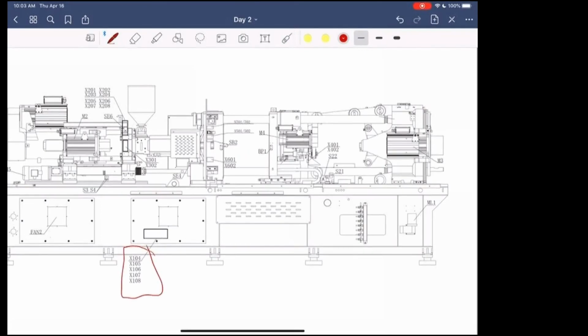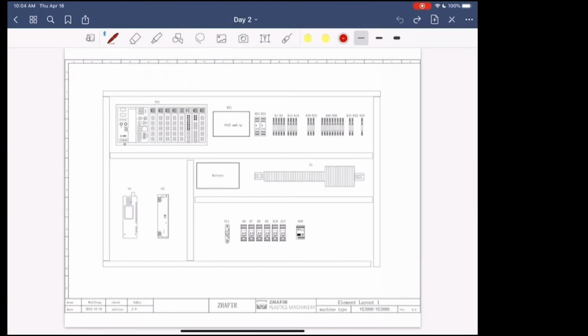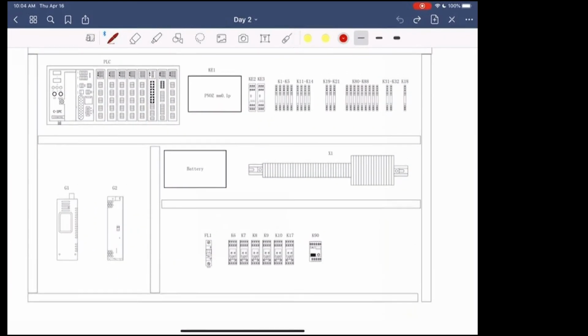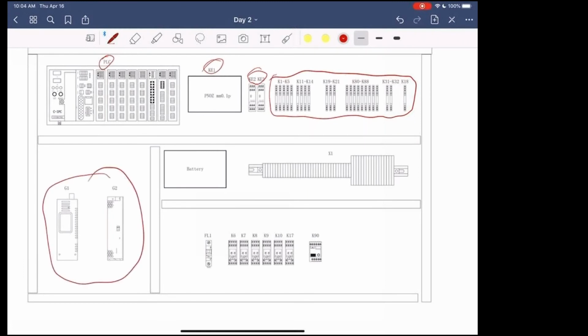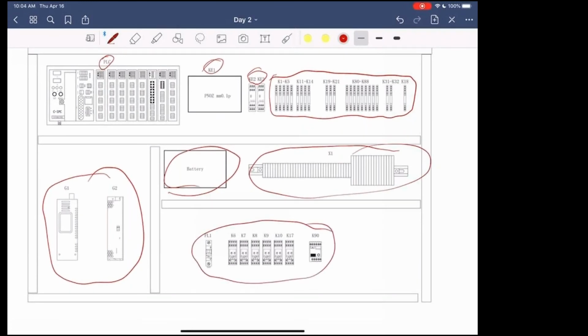For example, X1, 4, 5, 6, 7, and 8 are located inside this panel. And they give you an element layout. The element layout is this is the low voltage cabinet. It's just a layout of what the cabinet should look like. So up here you have your PLC, KE1, that's your safety relay, KE2 and 3, and a bunch of little contacts. Your 2 power supplies, a battery, a terminal strip, and a couple relays down here.